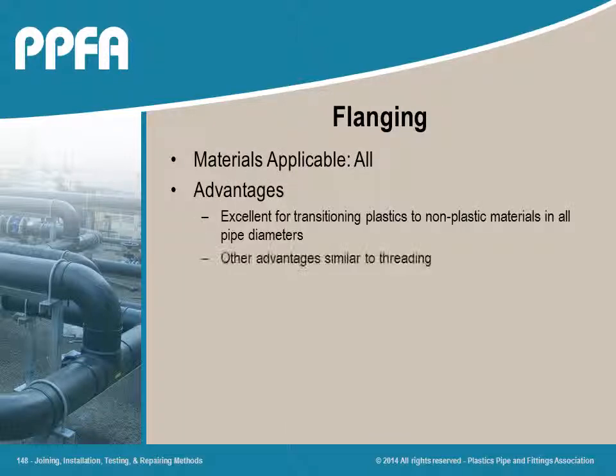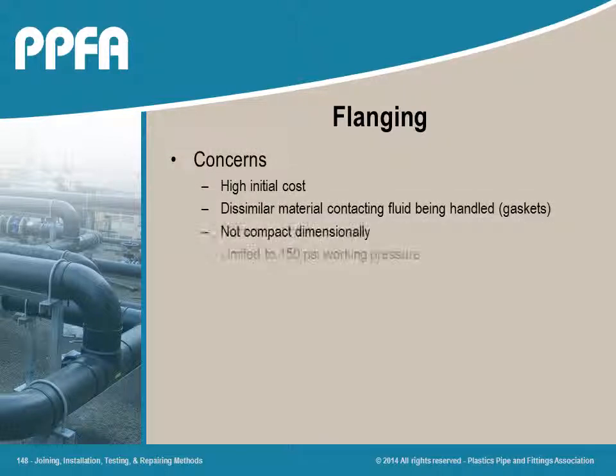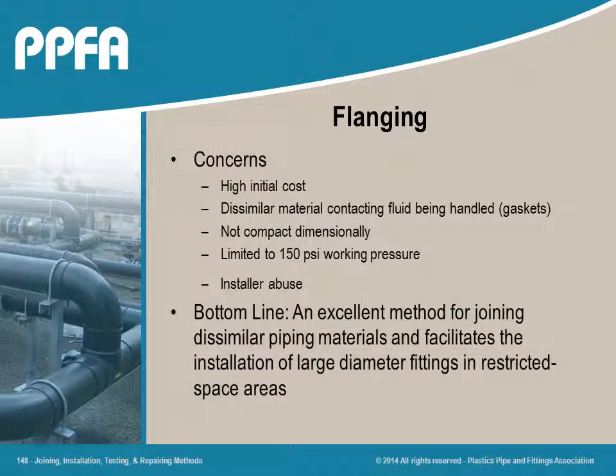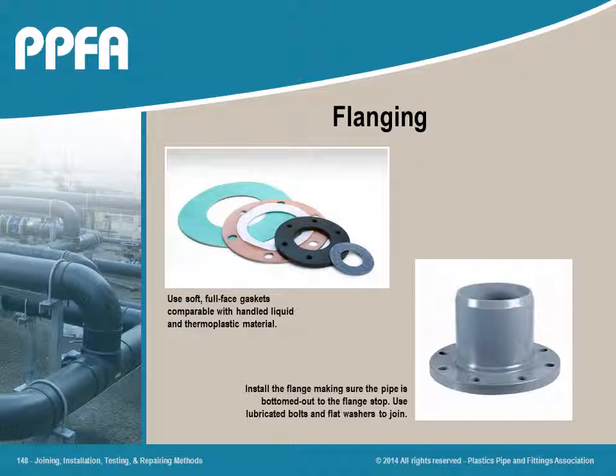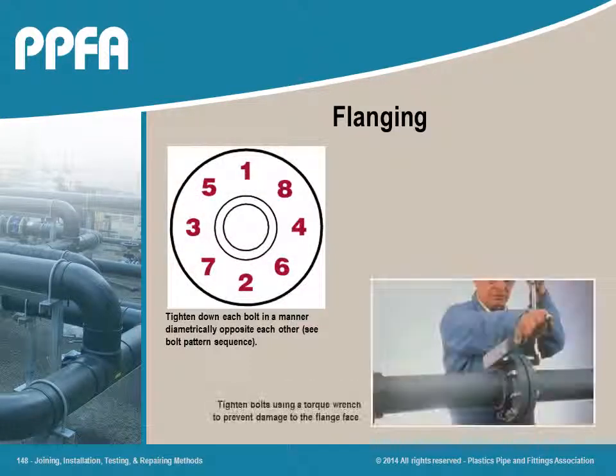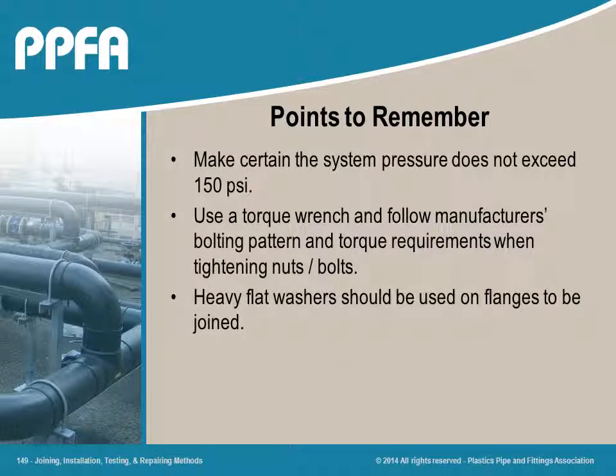The use of flanges allows dissimilar piping materials to be joined to one another and is especially useful for installing larger diameter pipes. Flanges also allow complex piping systems to be prefabricated in a controlled environment and then shipped to the job site. Flanging plastics is very similar to other flanging piping materials. Consider flanging when joining above ground large diameter piping and joining dissimilar piping materials.